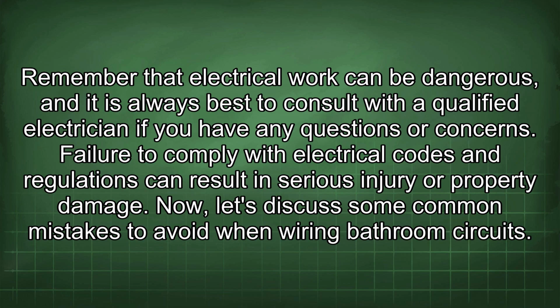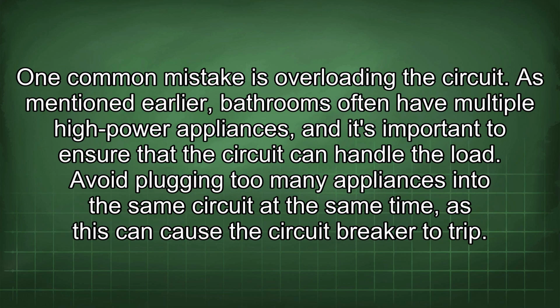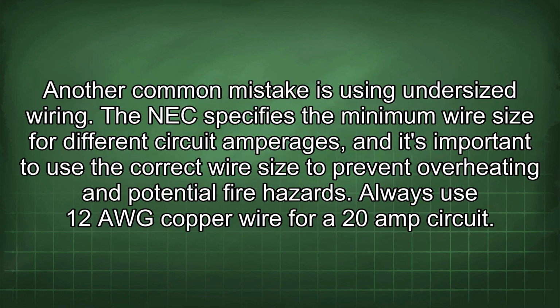Now let's discuss some common mistakes to avoid when wiring bathroom circuits. One common mistake is overloading the circuit. As mentioned earlier, bathrooms often have multiple high-power appliances, and it's important to ensure that the circuit can handle the load. Avoid plugging too many appliances into the same circuit at the same time, as this can cause the circuit breaker to trip. Another common mistake is using undersized wiring. The NEC specifies the minimum wire size for different circuit amperages, and it's important to use the correct wire size to prevent overheating and potential fire hazards.